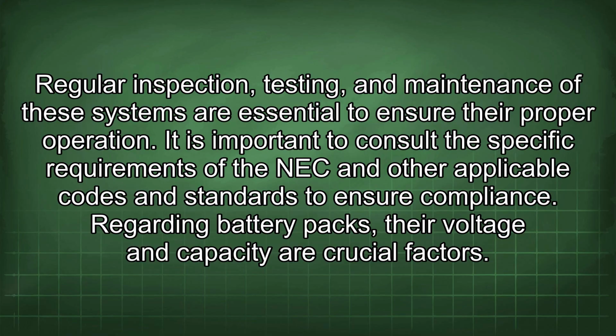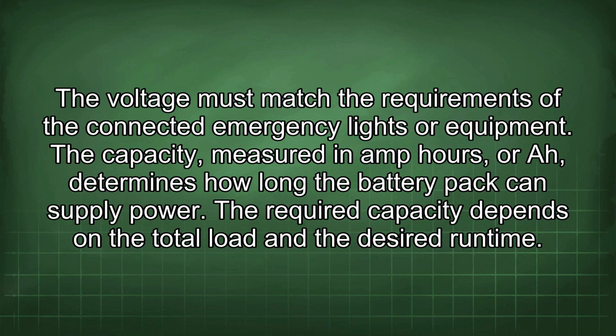It is important to consult the specific requirements of the NEC and other applicable codes and standards to ensure compliance. Regarding battery packs, their voltage and capacity are crucial factors. The voltage must match the requirements of the connected emergency lights or equipment. The capacity, measured in amp hours, or Ah, determines how long the battery pack can supply power. The required capacity depends on the total load and the desired runtime.